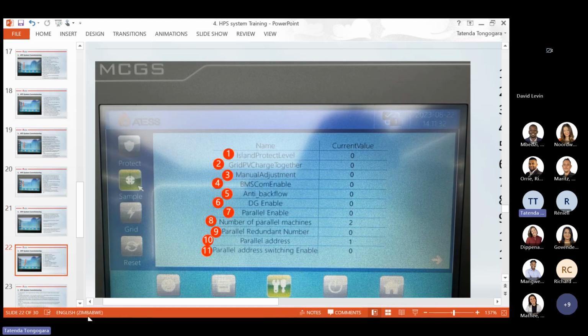And then below our protect parameters, we have the sample parameters, the sample calibration on some HPS versions. So we have island protect level. This level is from 0 to 9. This is how quickly your system switches, like the SCR, when the voltage of grid is low or high, or when you connect your generator, when your generator starts.